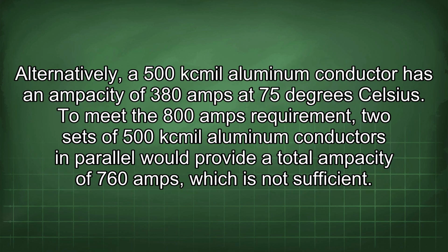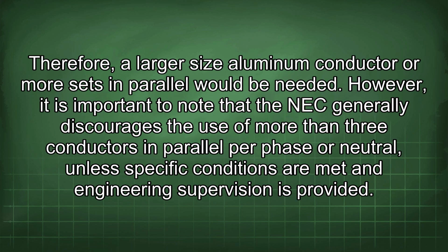Alternatively, a 500 kcmil aluminum conductor has an ampacity of 380 amps at 75 degrees Celsius. To meet the 800 amps requirement, two sets of 500 kcmil aluminum conductors in parallel would provide a total ampacity of 760 amps, which is not sufficient. Therefore, a larger size aluminum conductor or more sets in parallel would be needed. However, it is important to note that the NEC generally discourages the use of more than 3 conductors in parallel per phase or neutral, unless specific conditions are met and engineering supervision is provided.